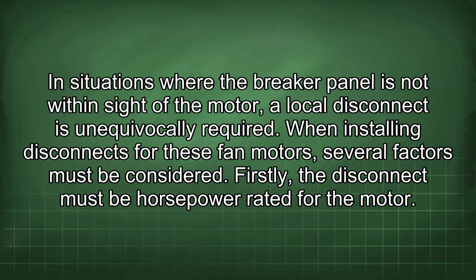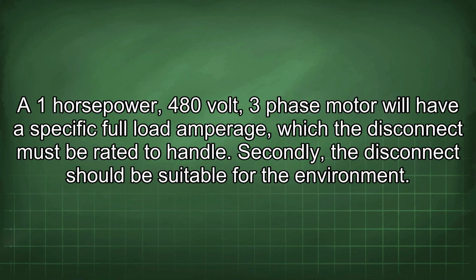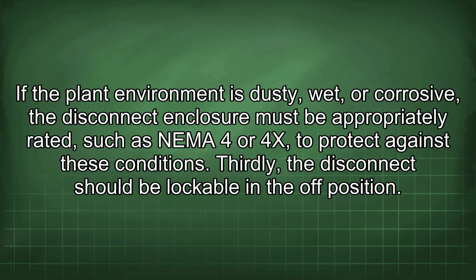When installing disconnects for these fan motors, several factors must be considered. Firstly, the disconnect must be horsepower rated for the motor. A 1 horsepower, 480 volt, three-phase motor will have a specific full load amperage, which the disconnect must be rated to handle. Secondly, the disconnect should be suitable for the environment. If the plant environment is dusty, wet, or corrosive, the disconnect enclosure must be appropriately rated, such as NEMA 4 or 4X, to protect against these conditions.